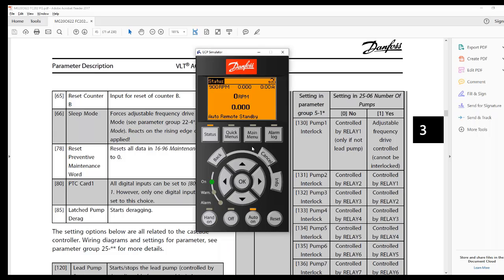So if I've set the DERAG and did all the power tuning, because the power tuning is done based on live settings, and then I did the AMA, and then the motor starts using less power, possibly we have to adjust the scaling factor to detect the clogged pump function at lower levels then. So if AMA was done before, will it affect it after I set it? No. But if I do AMA after and it changes the power that the motor's using to a lower level, just saving more energy, then basically those lines get farther apart. So kind of a yes and no.